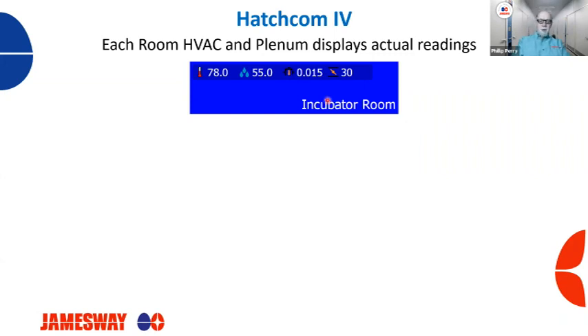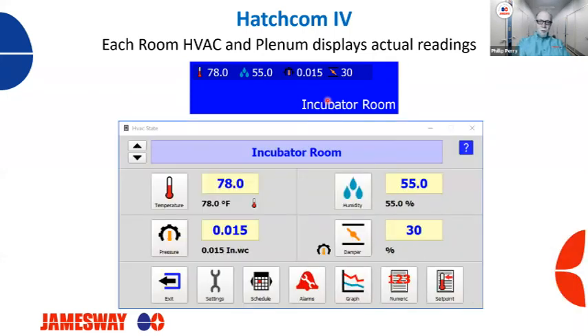When we double click on our icon, we bring up the room, and again, this HVAC state screen looks very similar to our platinum set point. Only we have our pressure. This is in inches water column. You can change your preferences if you'd want it in Pascals. It shows our damper position. It shows that it's in an automatic mode. It's not in manual. So this damper can be fluctuating to maintain our room pressure.